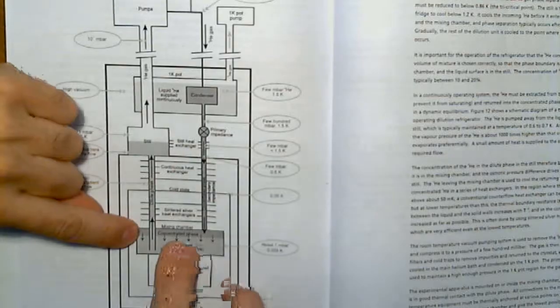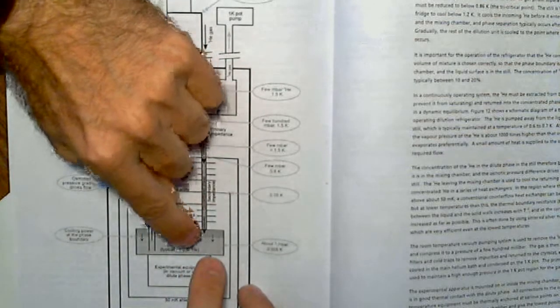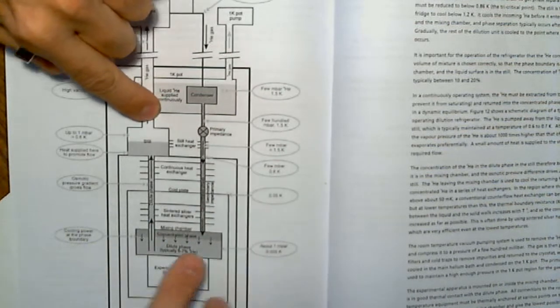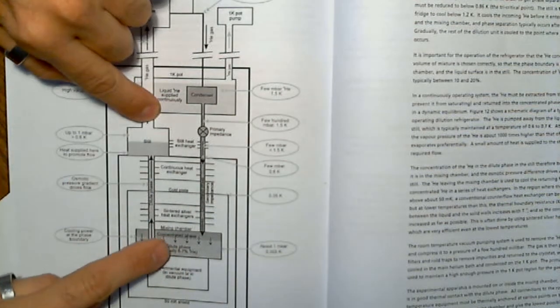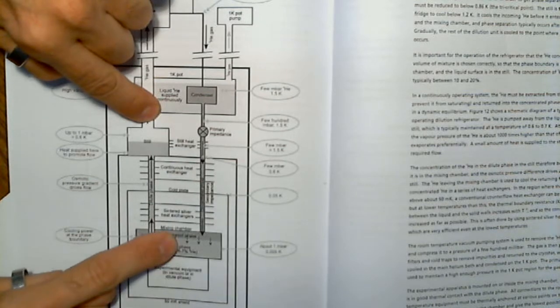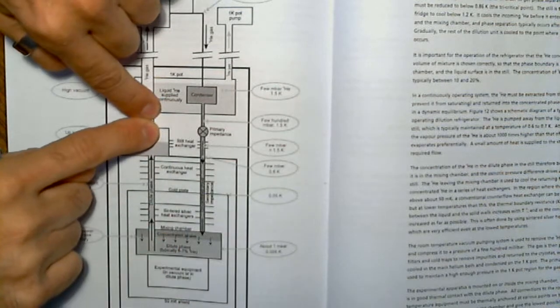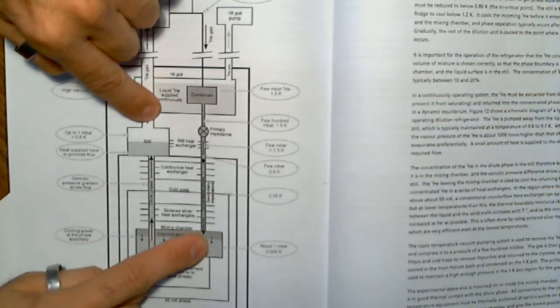You can imagine it like this in the drawing: here you have your phase boundary with two phases, helium-3 and helium-4. If you pump on the top, the helium-3 migrates from one phase to the other and gets pumped out. That's where the cooling happens.